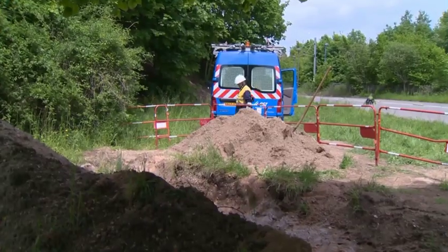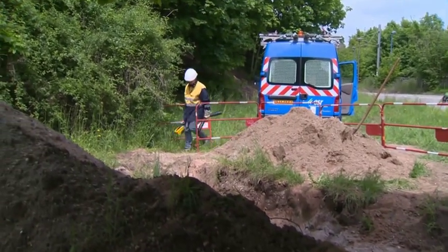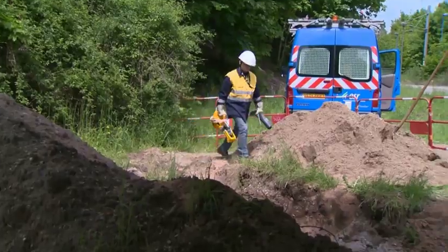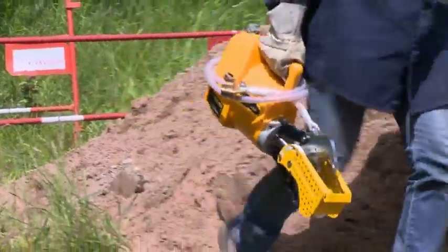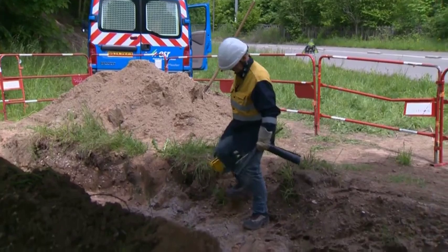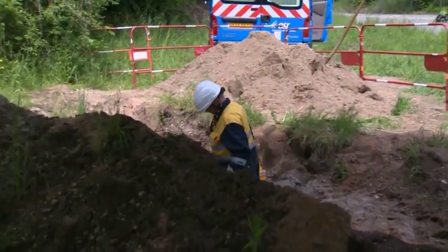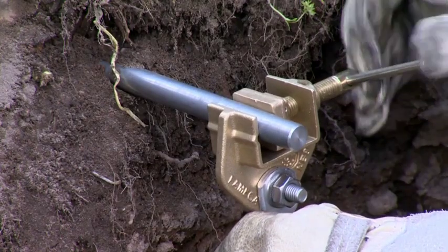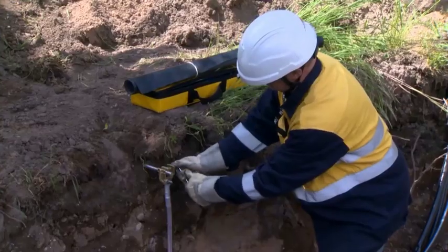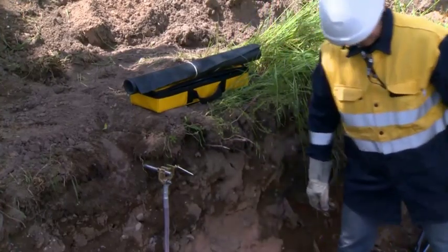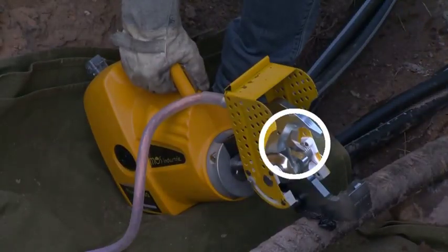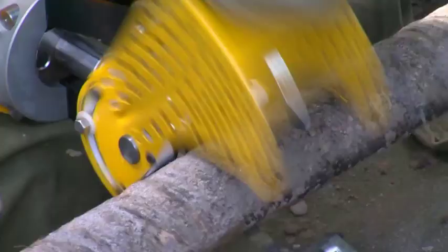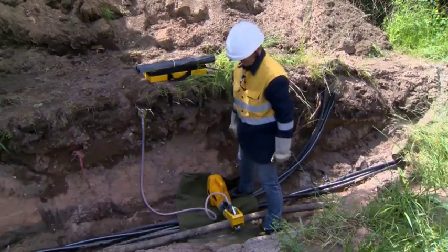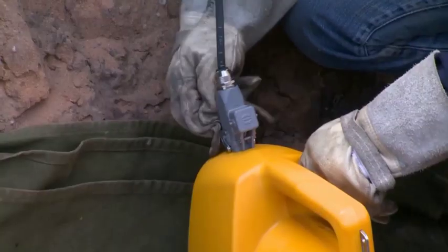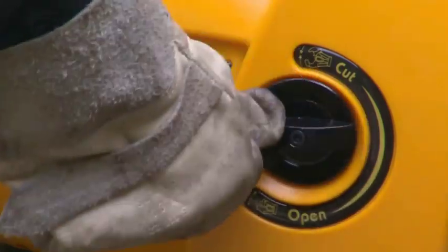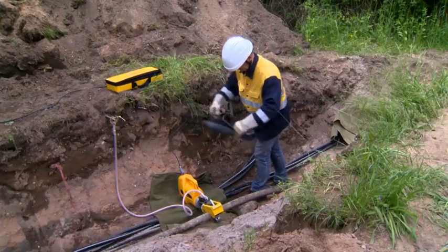The P-Coupe is an autonomous hydraulic device. When using this device, you link the spiking action for the voltage detection operation with the complete cutting of the cable. The P-Coupe offers two additional safety features in the event there's still voltage in the cable. Firstly, it is grounded to evacuate any remaining power into the ground or enable protective relays to trip circuit breakers. Its operating speed is calibrated to be certain of providing a unipolar fault, and also it is designed to ensure the complete protective sequence.